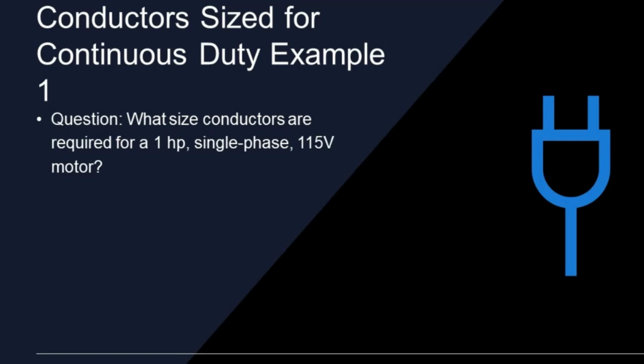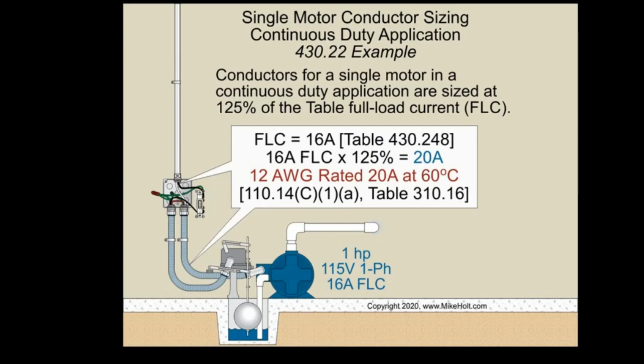Okay, so I'm going to go to single phase. So now I'm at table 430.248, right? I go to 115 volt motor. I go to 1 horsepower. It tells me I'm at 16. Okay. So now at 16, I multiply 16 by 1.25.